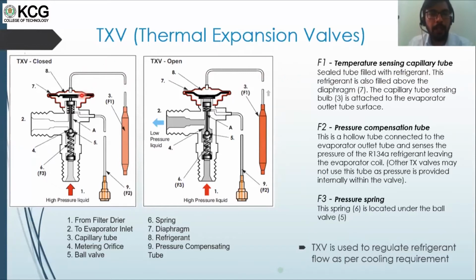So if your evaporator is initially in the running condition... okay, let me try to explain it this way. If your vehicle is in the off condition, your evaporator will be at ambient condition, so it will be hot. That heat will expand the refrigerant sealed in this TXV tube, so this diaphragm will get depressed. Here, as you can see, there is a ball valve. It will get depressed, and this is the TXV open condition, as this will allow the flow from the high pressure to the low pressure side. So initially your TXV will always be in open condition.